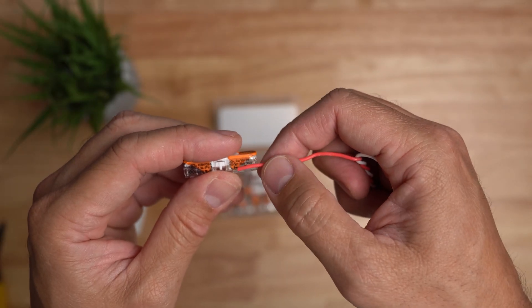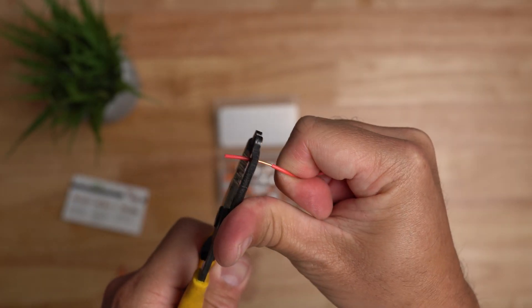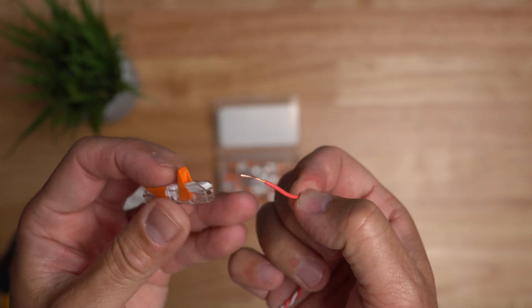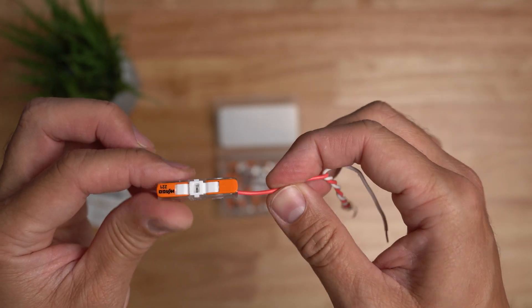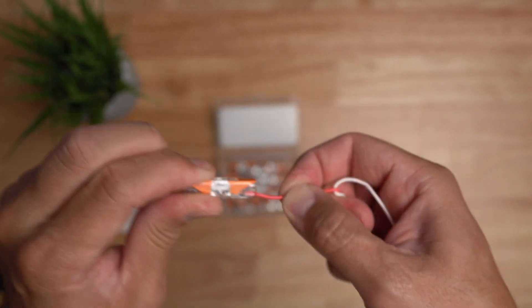There's a guide on the side on how long you need to strip the wire which is around 11 millimeters and flip the lever up, slide the wire in and flip the lever down. It locks it down that you will not be able to pull the wires out.